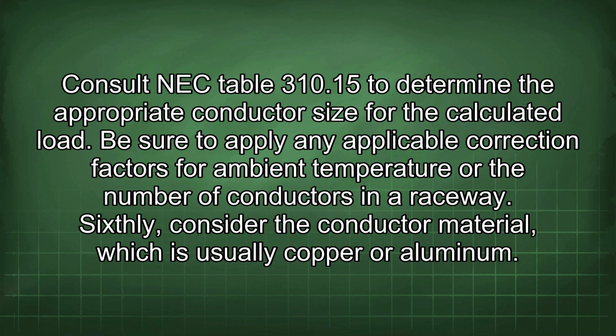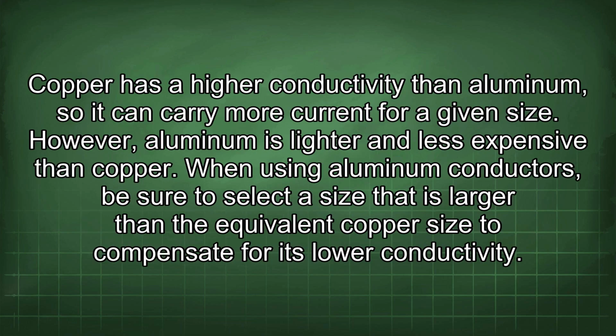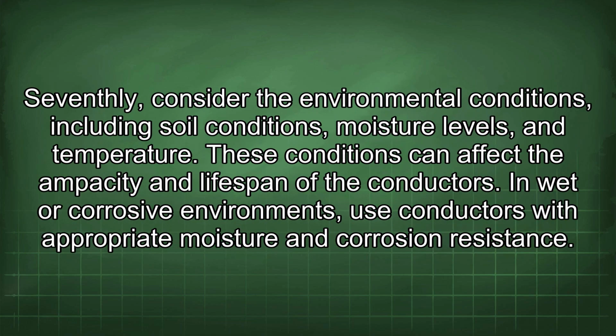Sixthly, consider the conductor material, which is usually copper or aluminum. Copper has a higher conductivity than aluminum, so it can carry more current for a given size. However, aluminum is lighter and less expensive than copper. When using aluminum conductors, be sure to select a size that is larger than the equivalent copper size to compensate for its lower conductivity. Seventhly, consider the environmental conditions, including soil conditions, moisture levels, and temperature.